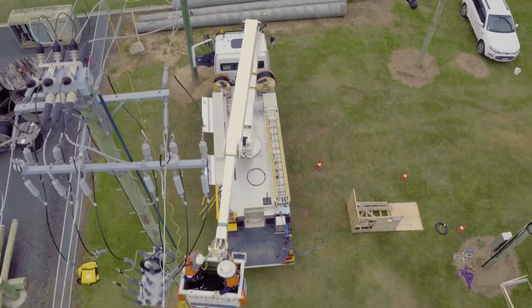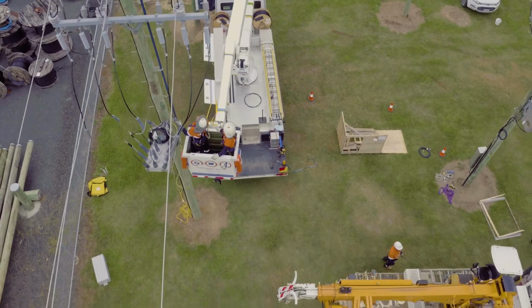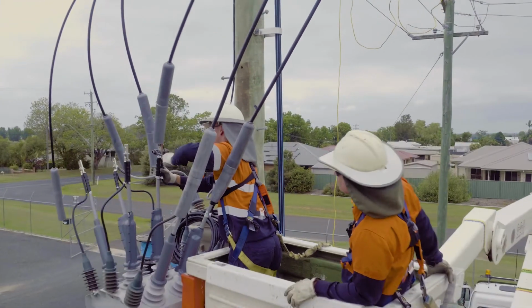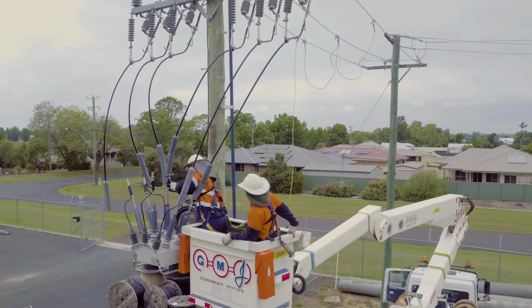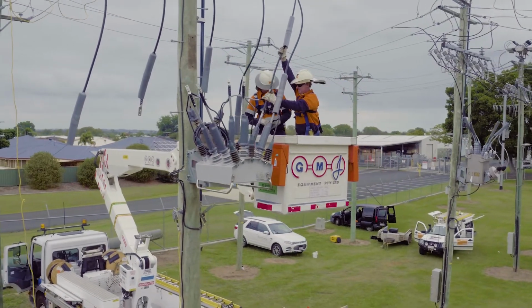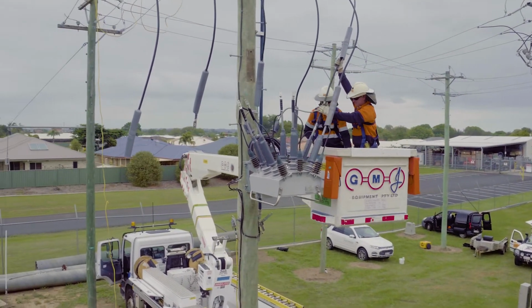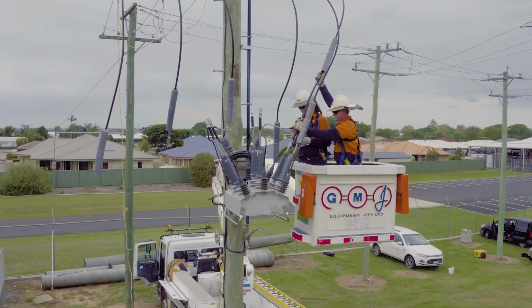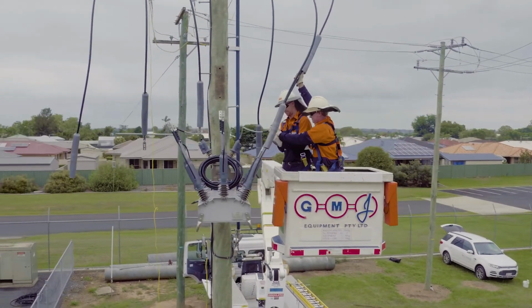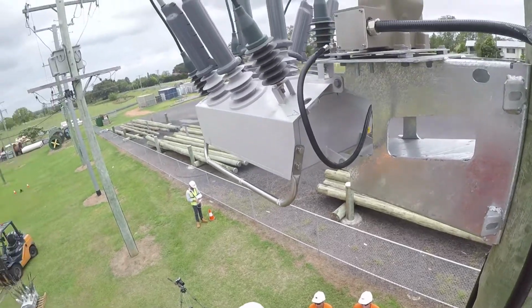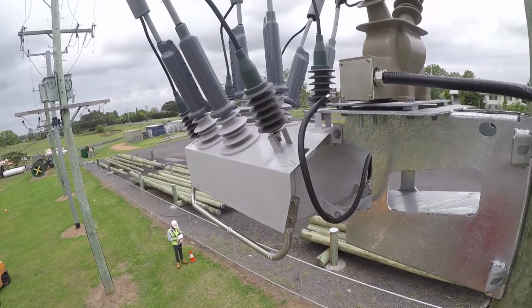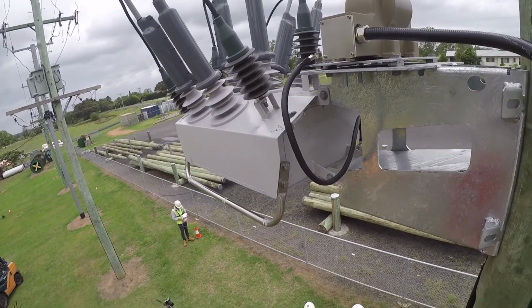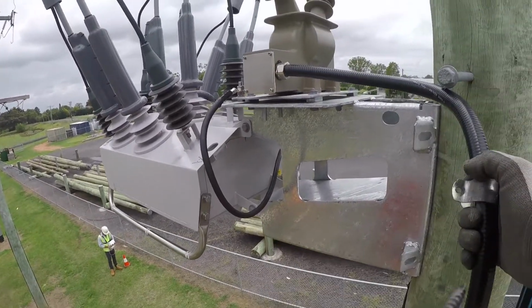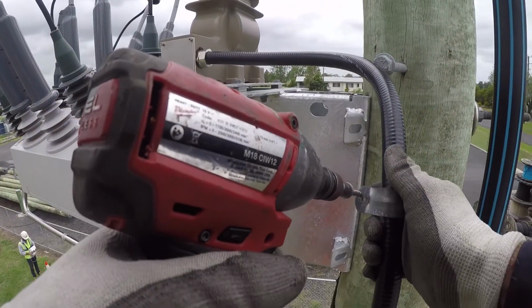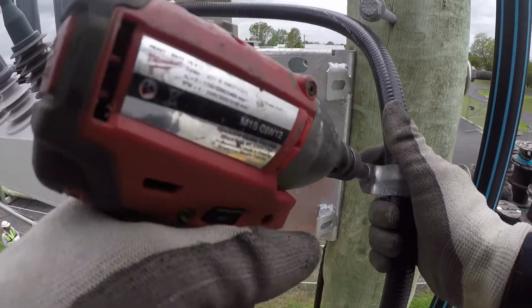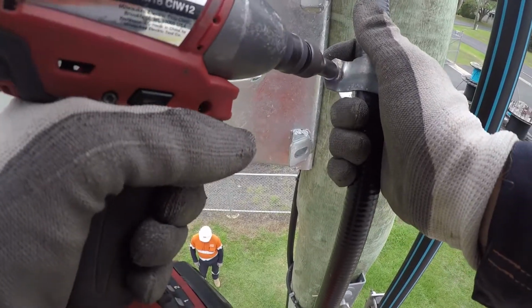Good earthing is absolutely essential for operator safety and to protect the recloser from damage. There are a few critical items that you'll need to take into consideration. NOJA Power specifies at least a 35mm square copper conductor for the earthing material. This should be spaced at least 200mm from the control cable so there is no possibility of flashovers between the lines. In areas with a high risk of vandalism or theft, the conductor can be run inside the pole or through some external protection such as a metal pipe.